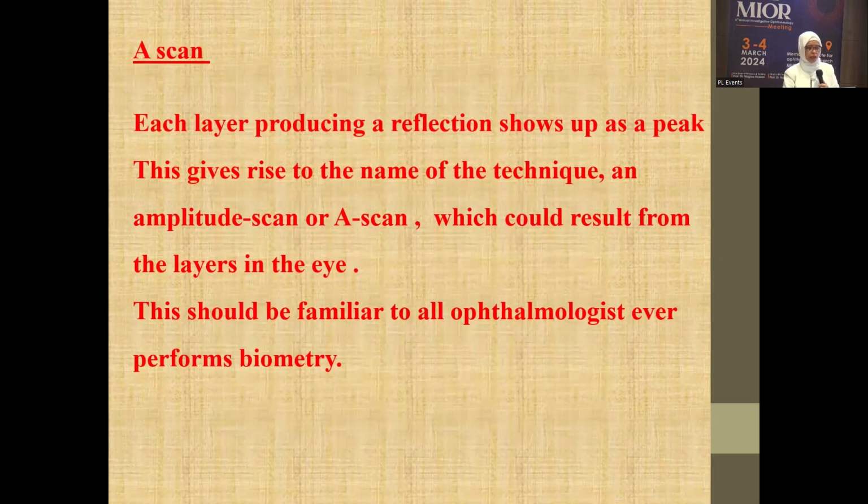A scan, each layer producing a reflection. Now we are talking about A scan echoes. Each layer producing a reflection shows up as a peak. This gives rise to the name of the technique, amplitude scan or A scan.